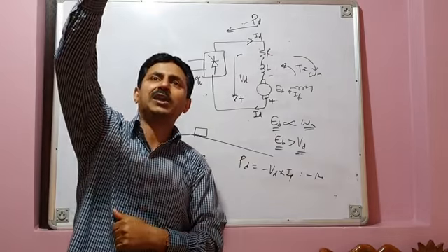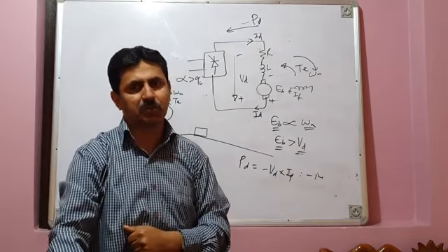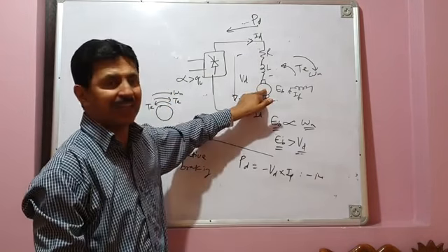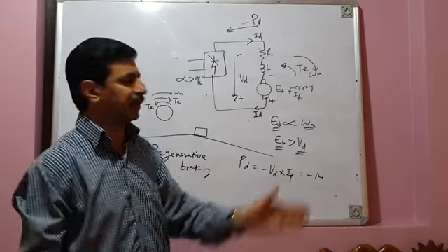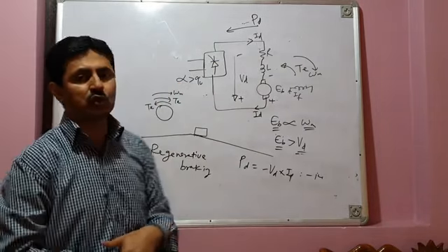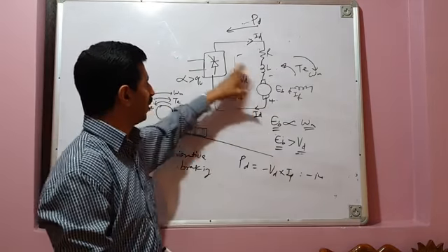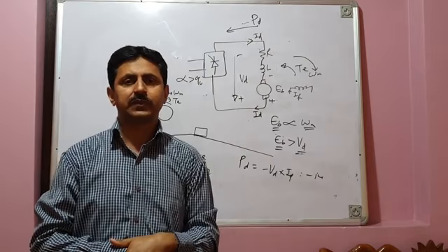So therefore from height, the machine comes down slowly at safe speeds, and simultaneously whatever energy you are generating, which is called braking energy, you are not wasting. You are feeding that braking energy back to the source. This is called regenerative braking. The advantage is that braking energy is not wasted, it is fed back to the source.